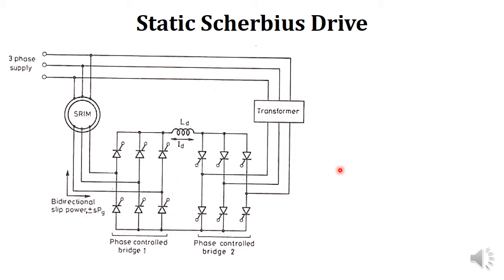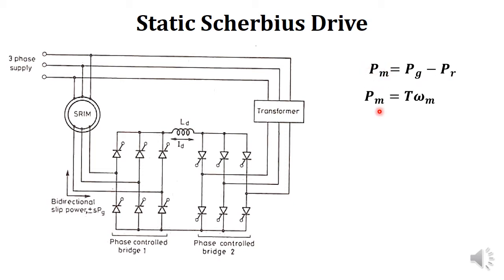Let's consider the basic equations for slip power recovery schemes. The first equation is: Pm = Pg − Pr, where Pm is the mechanical power, Pg is the air gap power, and Pr is the slip power. Using slip power recovery schemes, we control the amount of Pr. If we are able to control Pr, then Pm can be controlled, and if Pm is controlled, speed is controlled.